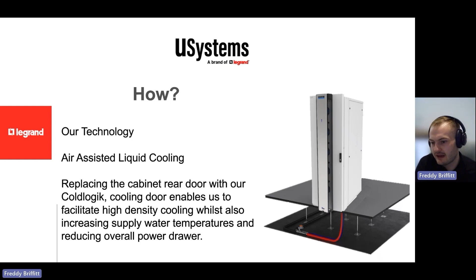But what we do have is a rear door that has a coil of warm water in it - you can see the pipework connections to it at the bottom of the screen there. We have our liquid very close to the source of the heat. So when I said the energy required to change the state of water is massive, the closer we can get the water to the heat source, i.e. the servers, the less temperature change we have to have within the water itself, which means the equipment behind that is working less hard, which really helps reduce the overall power.